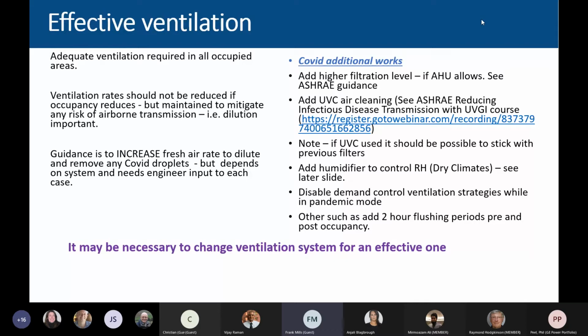Or we could put ultraviolet air cleaning in the ducts. That doesn't tend to have too much resistance to flow because there are gaps between the lamps for the air to flow. There is some resistance, but it's not a high one. But that then has to follow a particular procedure, and I've quoted the ASHRAE site here, and you can have a look at that. If you do use ultraviolet light, it's probable that you can stick with the filters that are in at the moment, because the filter is really just, in my terms, keeping the lamps clean. It's not trying to remove the virus, because the UV is going to do that.